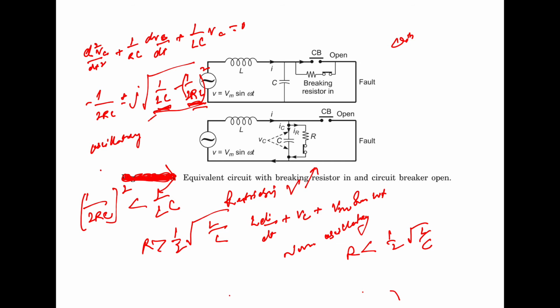The response will be critically damped if R equals (1/2)√(L/C). So the rate of rise of restriking voltage and its maximum can be controlled by suitably choosing the value of this breaking resistance R.